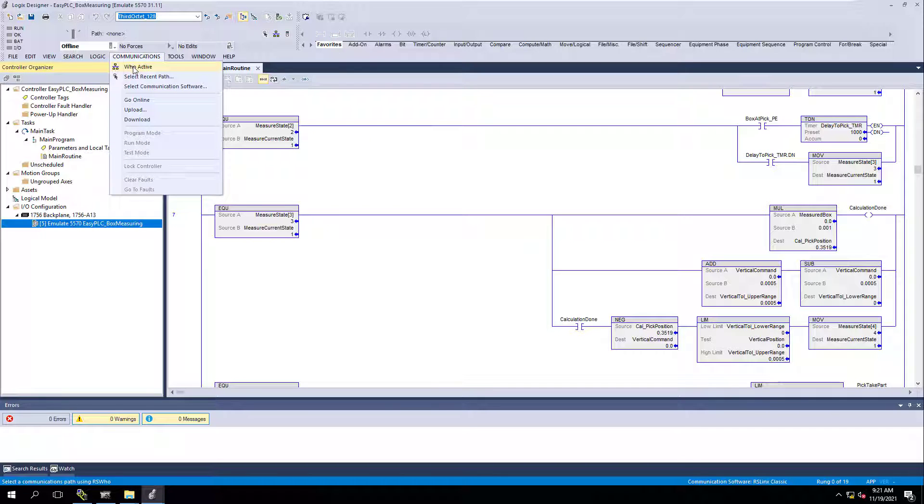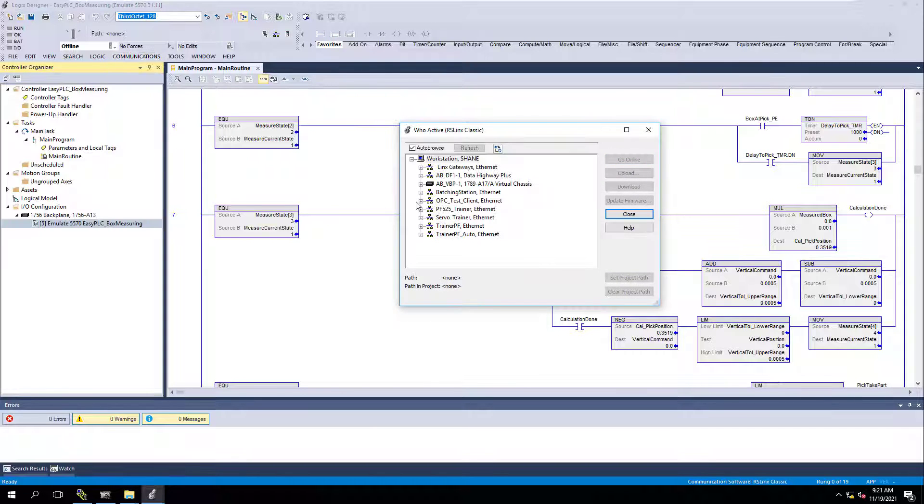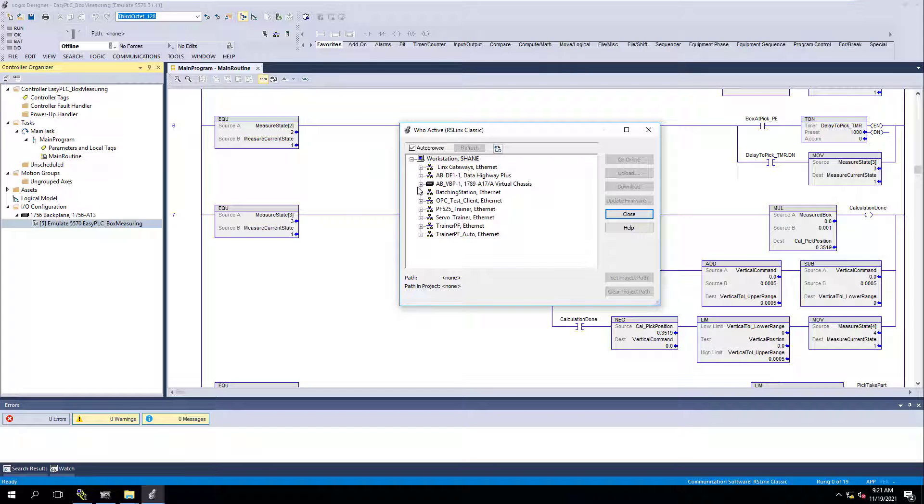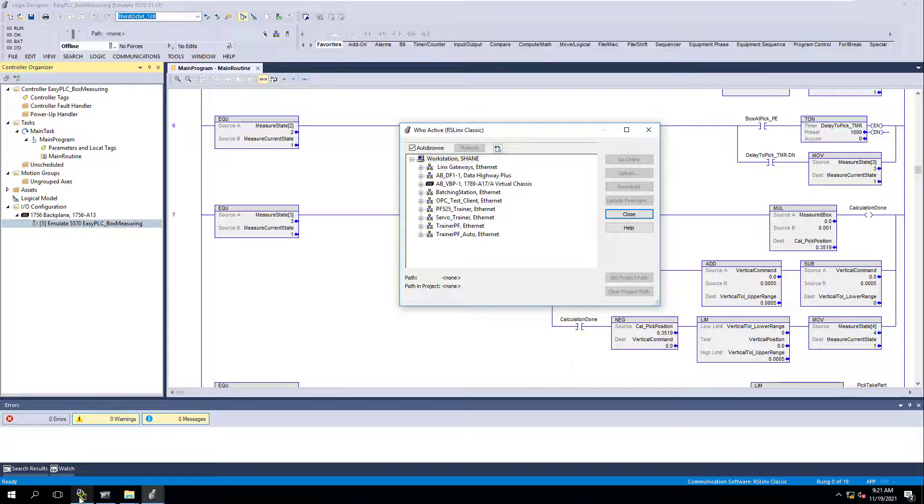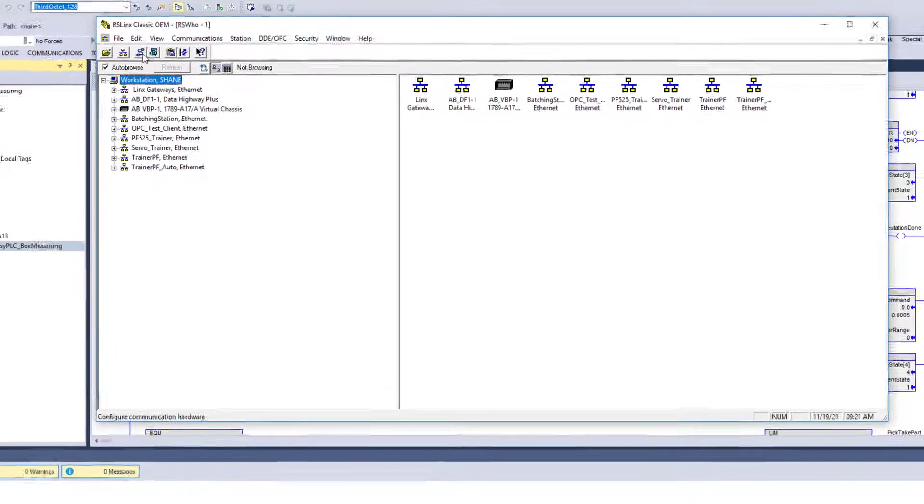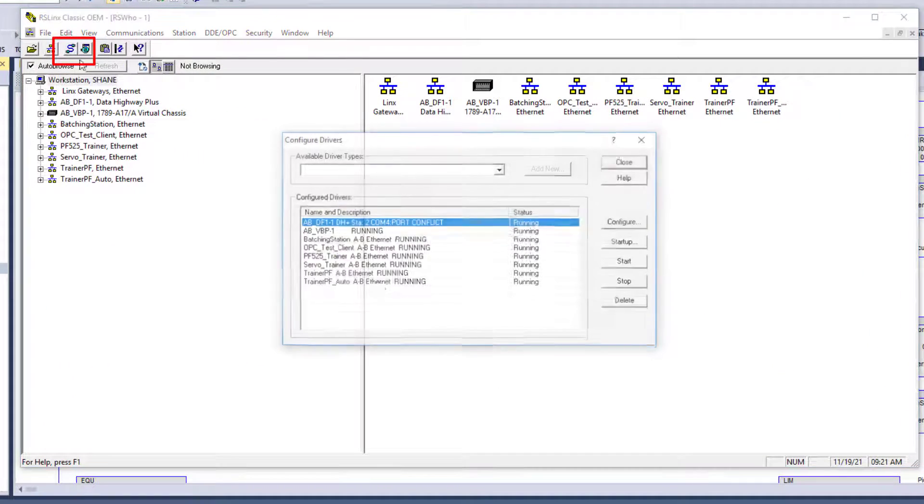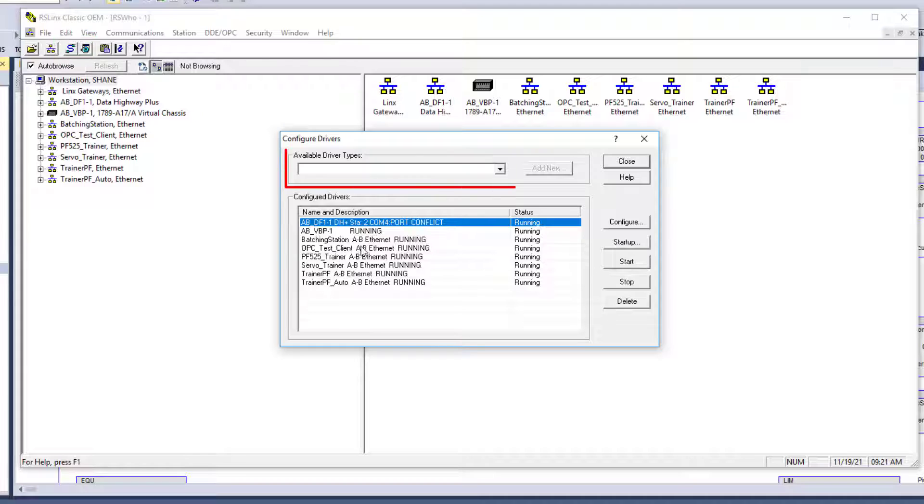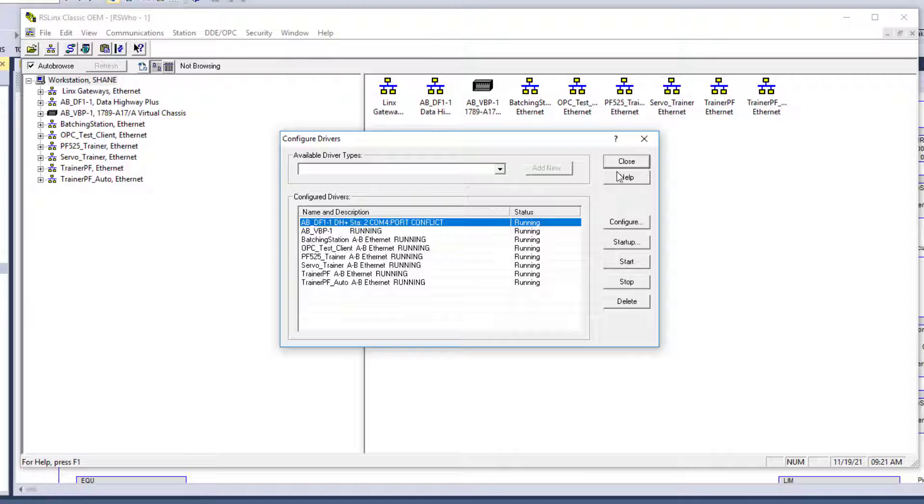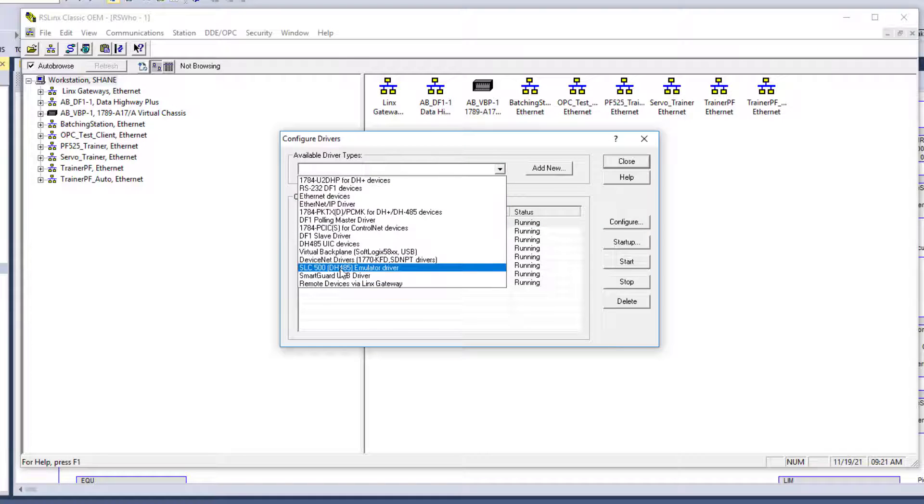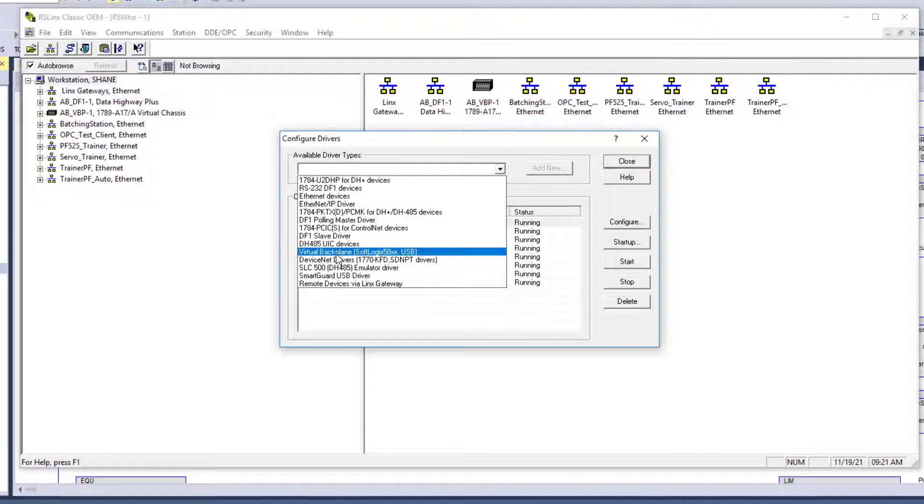What we've done is our processor was in slot five. We've actually added our processor. So now we have the ability to download. We're going to go to communications, who active. Now here's the kicker. If you don't have all of your drivers in here, make sure you open up RSLinx and you go to your driver, add your configured driver. And then what you're going to do is add in, for instance, this is going to be a virtual backplane. So this would be your driver.